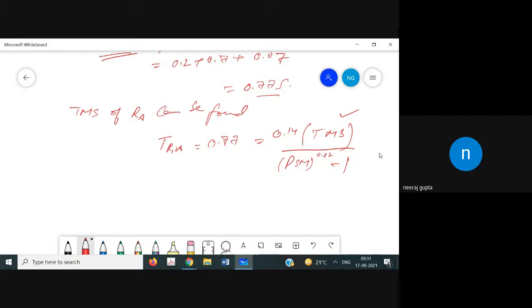And as you know, in the case of relay A the CT ratio is 300 is to 1. So the current across the relay is 3000, and we have to calculate the PSM, because we are considering the maximum current at relay B. We are doing the setting as per the maximum current at relay B, not relay A. So it is divided by the CT ratio, that is, we have here I relay and the plug setting.